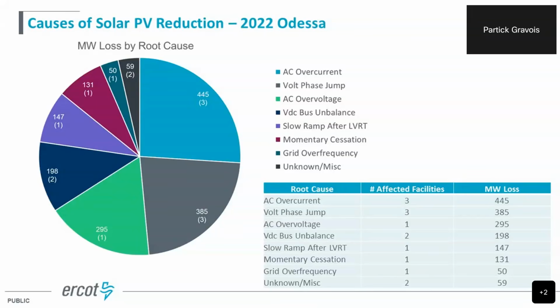All right, again, we went through the RFI analysis, we went through follow-up calls with all facilities looking at the root cause analysis, and these are the results of all that work. We're seeing a different set of root causes. The largest this time was AC overcurrent, which is something we didn't see in the 2021 event. Volt phase jump is a new one as well. This is similar to the PLL; we disabled the PLL loss of sync, and now we're seeing the volt phase jump instead. Overvoltage is still there, and we've got a couple of other ones. The VDC bus imbalance is a new one, and then we've got 2 of the other facilities as well.